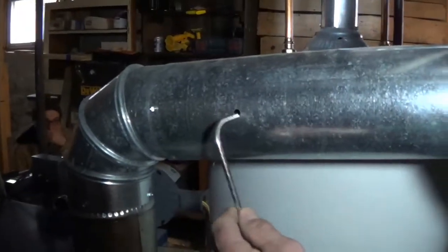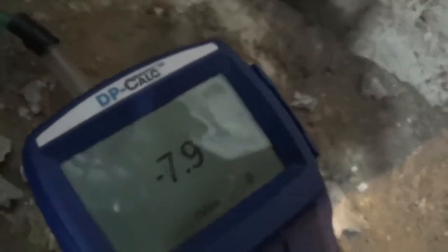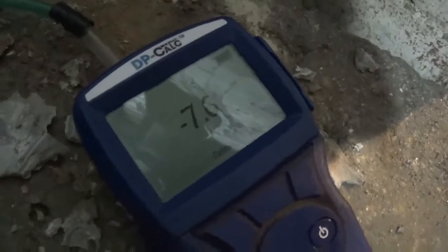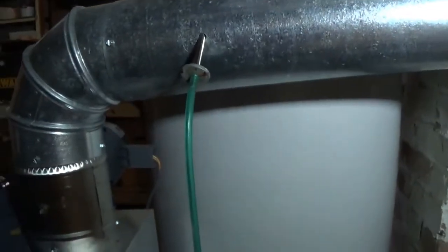Now let's find out what the draft is. You will see that draft can pass, but spillage will still fail. It's still a fail. Draft passed all ways so far. The heating system was close to failing under worst case. Sorry, it did fail under worst case by minus 0.125. But so far under natural conditions, the draft for everything is A-okay. And again, you see that, but spillage is still spillage.